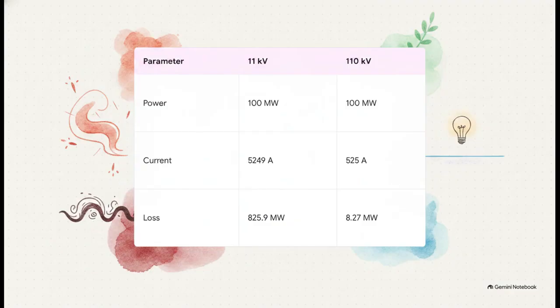Let's look at this in action with a direct comparison—the ultimate aha moment. Both scenarios transmit the exact same 100 megawatts. On the right side, we've stepped the voltage up 10 times, from 11 kilovolts to 110 kilovolts. As a result, the current drops from over 5,000 amps down to just 525 amps. And the loss plummets from that catastrophic 825.9 megawatts down to a highly manageable 8.27 megawatts.